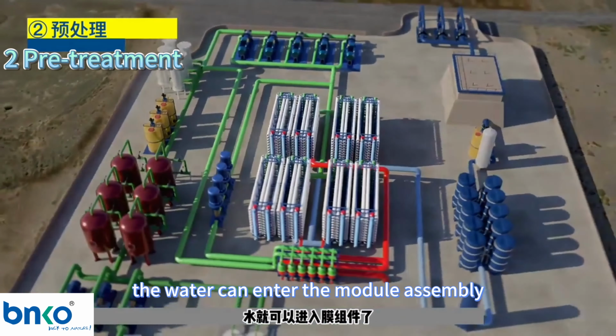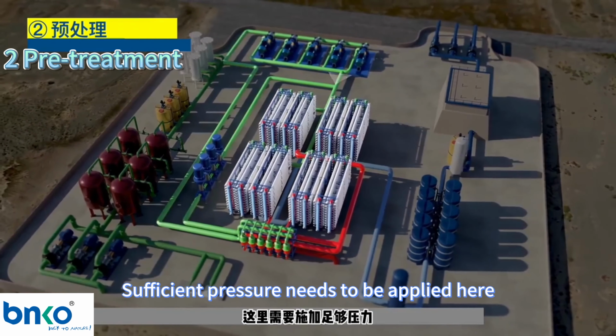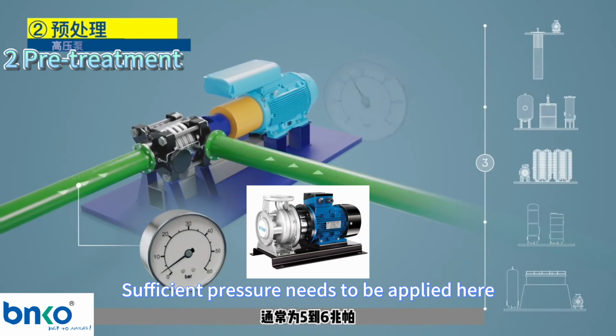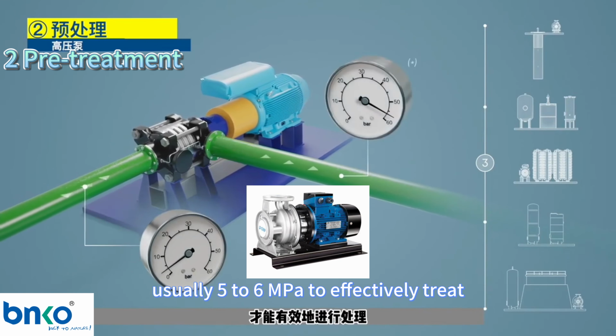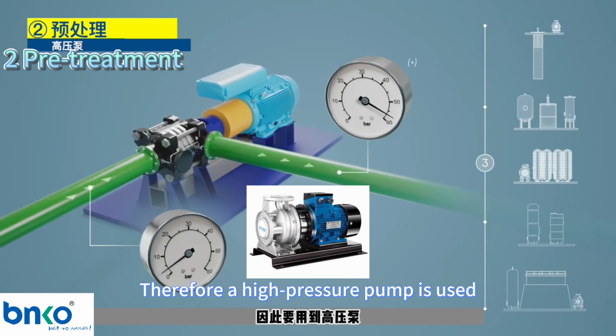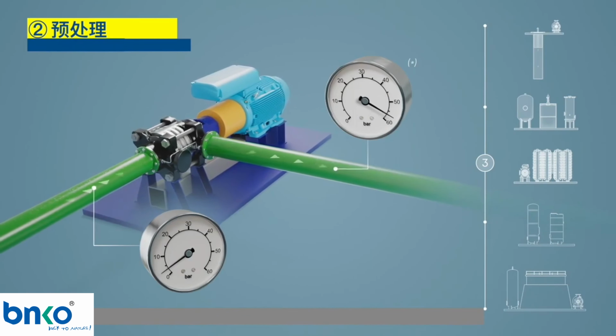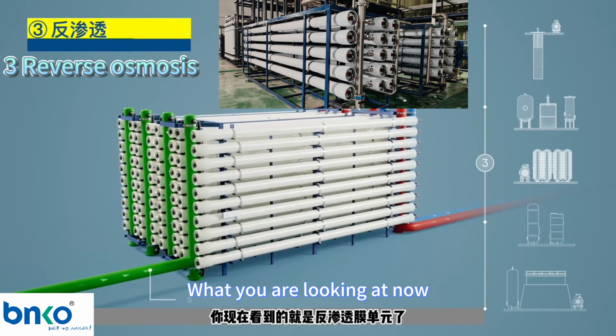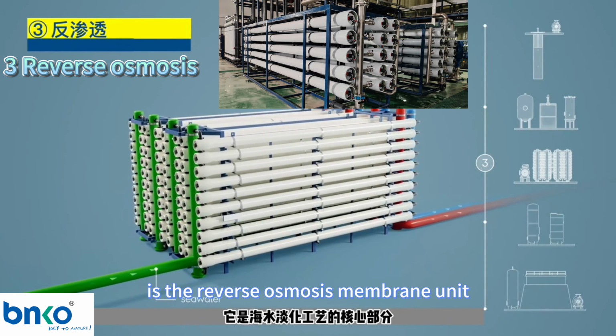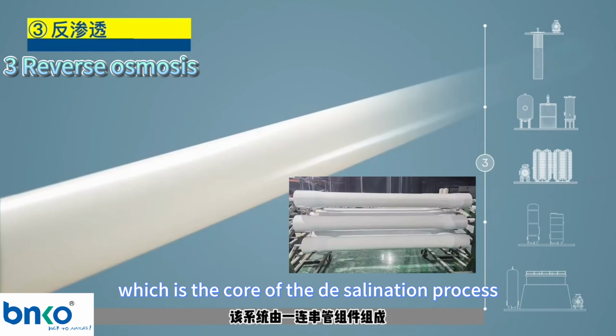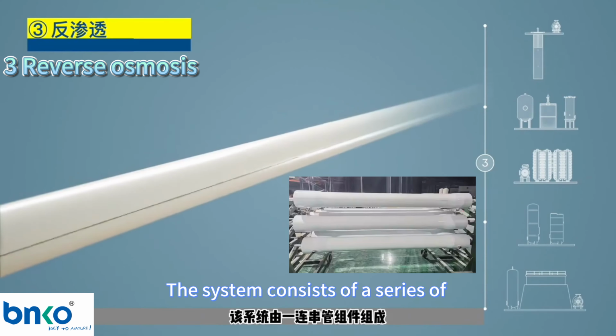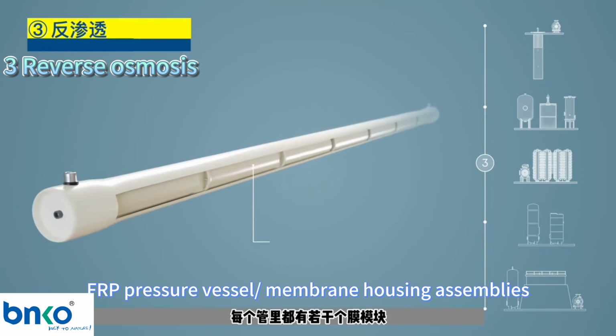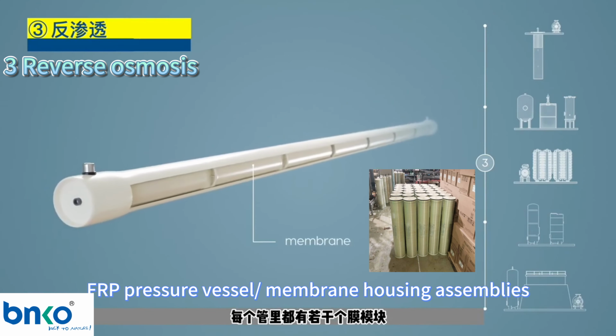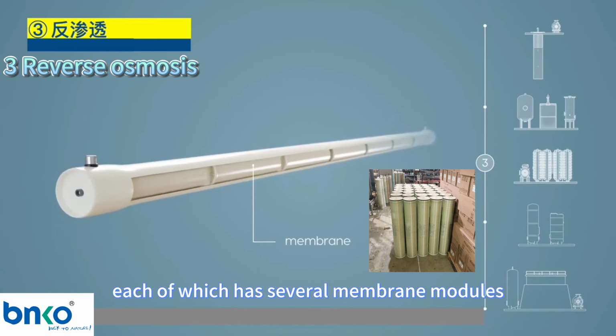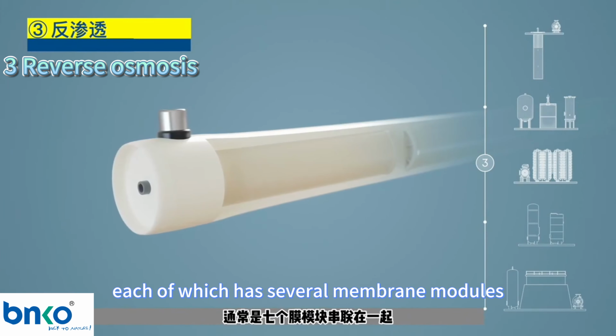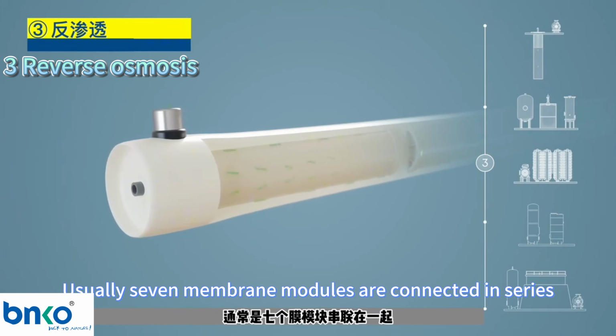After pretreatment, the water can enter the module assembly. Sufficient pressure needs to be applied here, usually 5 to 6 MPa, to effectively treat it. Therefore, a high-pressure pump is used. What you are looking at now is the reverse osmosis membrane unit, which is the core of the desalination process. The system consists of a series of FRP pressure vessel membrane housing assemblies, each of which has several membrane modules.